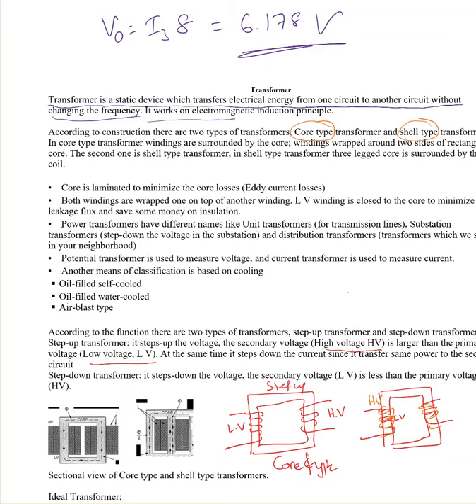Instead of calling them primary and secondary, we call them high voltage and low voltage. Primary is connected to the source, secondary is connected to the load all the time. HV and LV are nothing but high voltage and low voltage. For any type, either core type or shell type, there is always LV winding first.